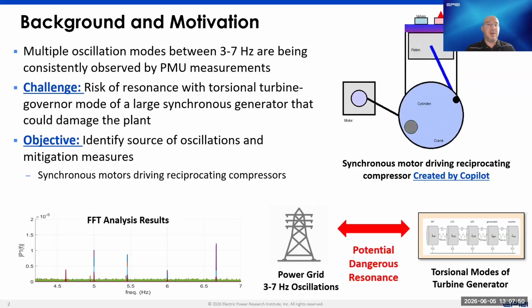between those oscillations and the torsional mode of that turbine generator system that they were upgrading. So there were concerns about potential damages in the plant and things like that. The objective of the study was to use recorded PMU data and try to identify what is causing these oscillations and what the source is, and suggest potential mitigation measures and detailed studies that would need to be done to identify the most practical and cost efficient way to mitigate that risk.